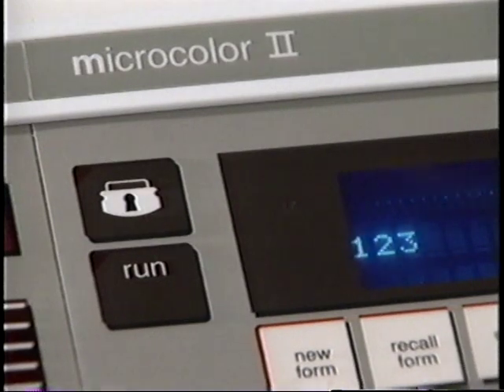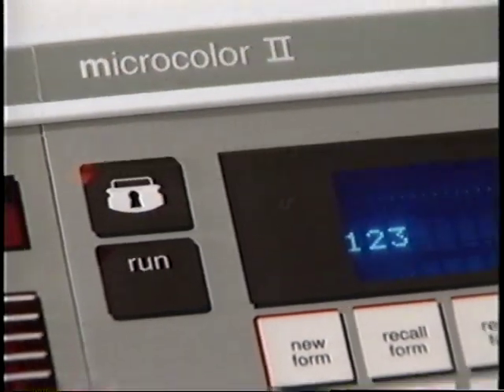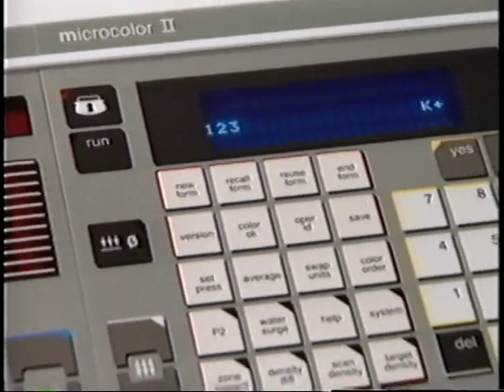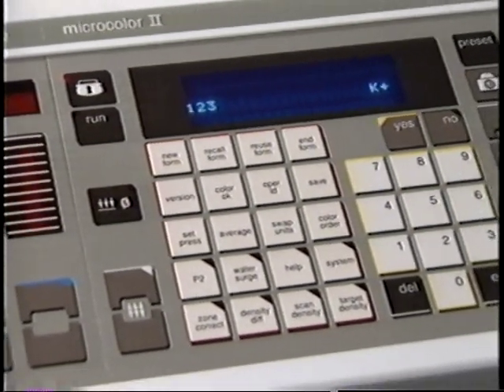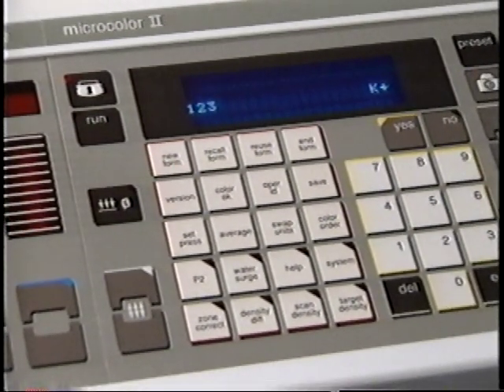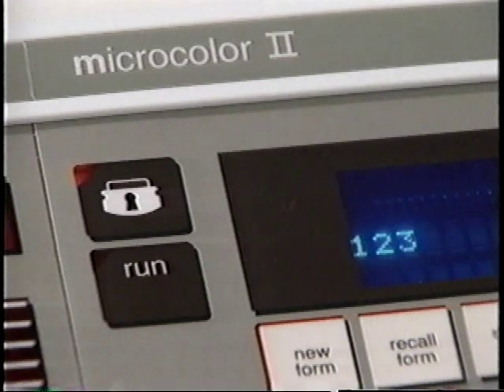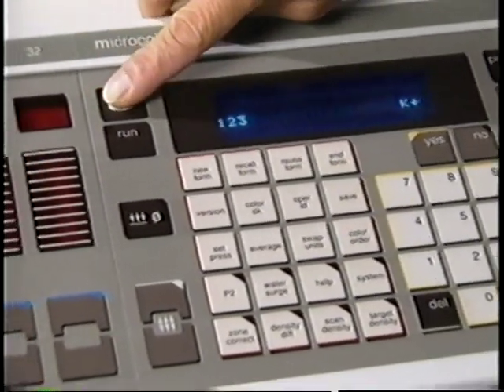The Lock button is a toggle that locks the console settings. When the lock is on, the red light comes on. The other console buttons will not respond until the lock is off. It is a good idea to push the Lock button when leaving the console unattended. This will prevent accidental changes to zone settings. To turn off the lock, push the button a second time.